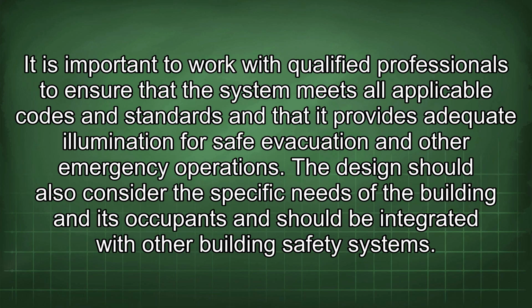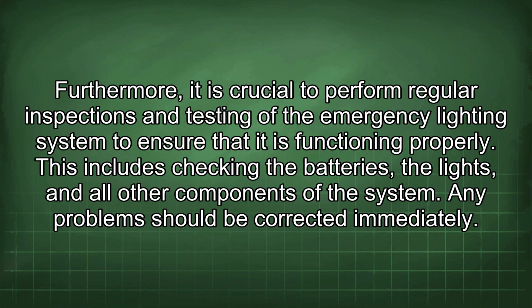It is important to work with qualified professionals to ensure that the system meets all applicable codes and standards and that it provides adequate illumination for safe evacuation and other emergency operations. The design should also consider the specific needs of the building and its occupants and should be integrated with other building safety systems. Furthermore, it is crucial to perform regular inspections and testing of the emergency lighting system to ensure that it is functioning properly. This includes checking the batteries, the lights, and all other components of the system. Any problems should be corrected immediately.